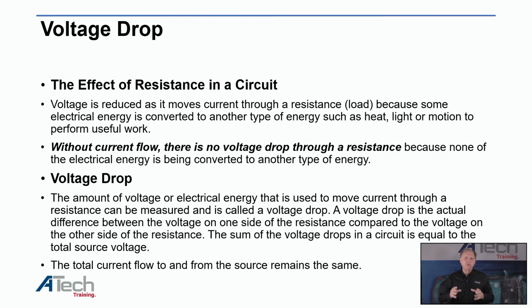You have to have current flow. If you don't have current flow, you're not going to have a voltage drop. I see a lot of guys trying to test a circuit with the circuit off. Continuity, yes, but you're not going to be able to do a voltage drop or current flow. It does not work. Your circuit has to be active to do that. You've got to teach that to everybody.